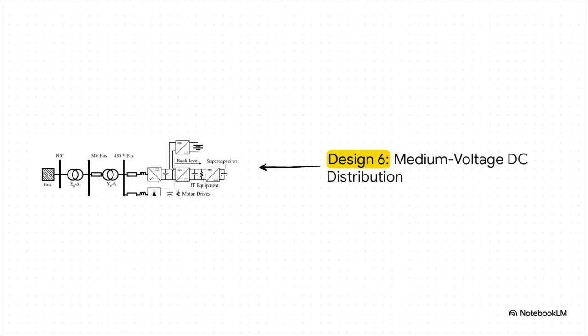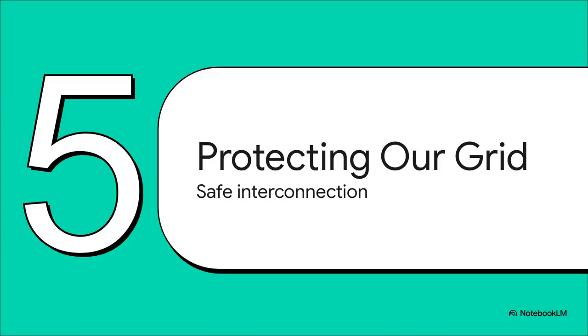Finally, we reach the totally futuristic Design 6, medium voltage DC distribution. In this setup, even the facility's medium voltage distribution network becomes entirely DC. That means removing heavy AC switchgear and traditional circuit breakers almost entirely from the critical path. It's going to require a massive supply chain evolution, but it just proves how radically artificial intelligence is reshaping foundational power engineering.